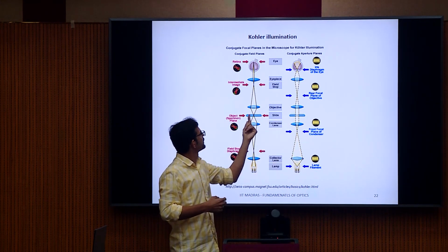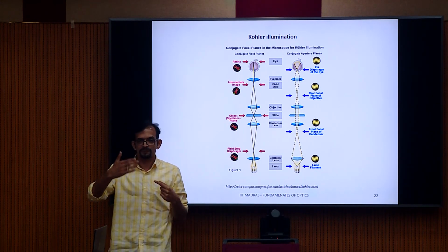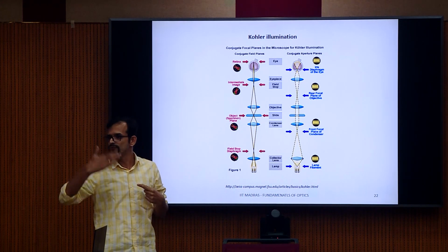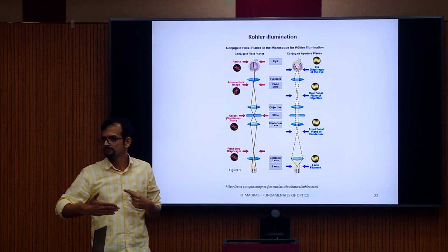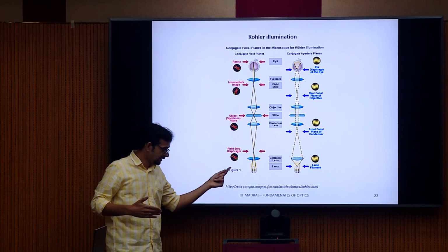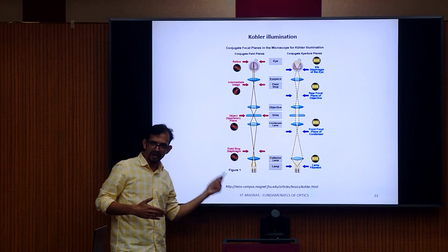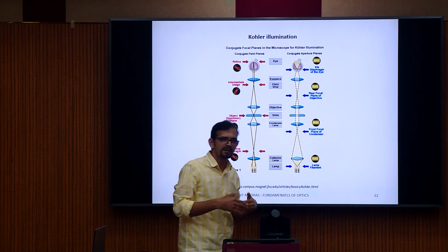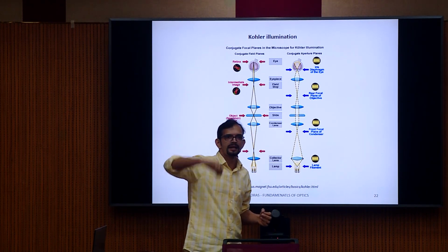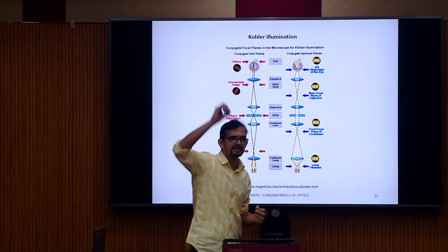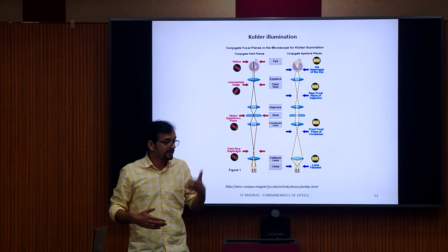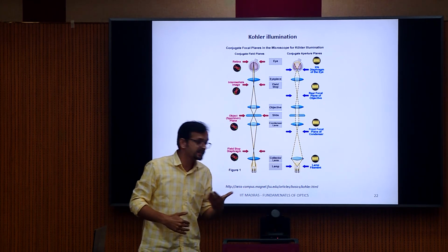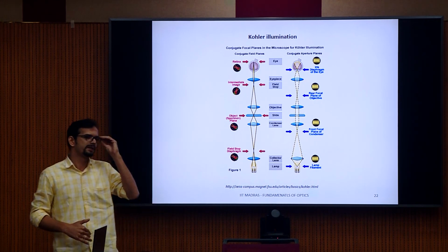So you will get the object perfectly imaged in a uniform background. This is called Köhler illumination. This is really important to have proper microscopy images. Sometimes we do grayscale image processing, intensity plots, but if your imaging illumination is not proper, everything is gone. Okay.